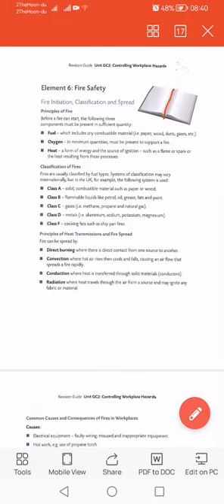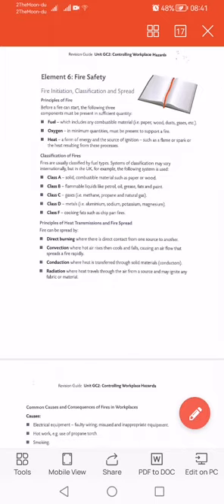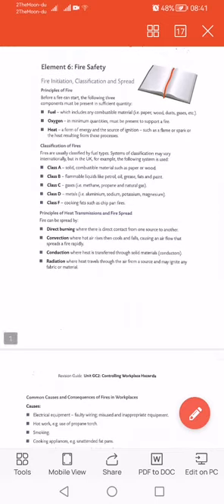Class A fire involves solid combustible material such as paper or wood. Class B fire is a flammable liquid like petrol, oil, grease, fat, or paint. Class C fire involves gas such as propane and natural gas. Class D fire involves metals like aluminium, sodium, potassium, magnesium, and boron. Class F fire involves cooking fats such as chip pan fires.